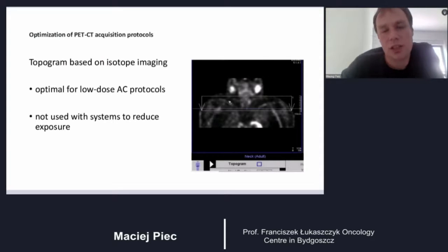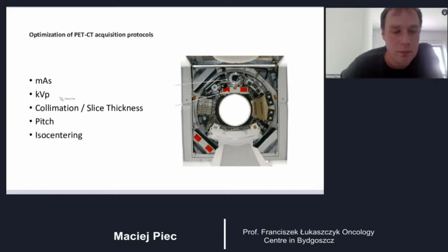And there are topograms based on isotope imaging, or on counts from isotope imaging. Well, that's more true for SPECT equipment, but I also heard that for PET it is possible. You need to be careful, because this is a very nice method to reduce the dose, because we are using the isotope already administered to the patient. But I'd like to draw your attention to the fact that the system of dose control will not work at this moment. So we'll be scanning the patient based on old parameters, which will impact the dose. But if we use low dose parameters, then we can work effectively, and the dose can be reduced.